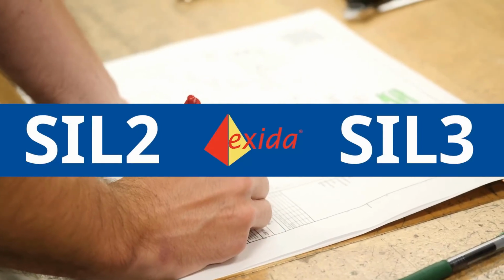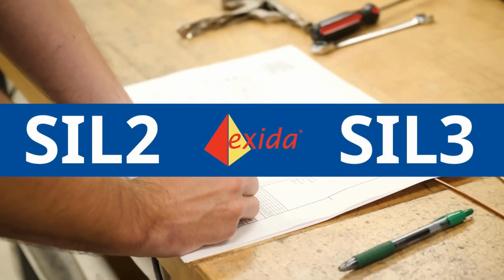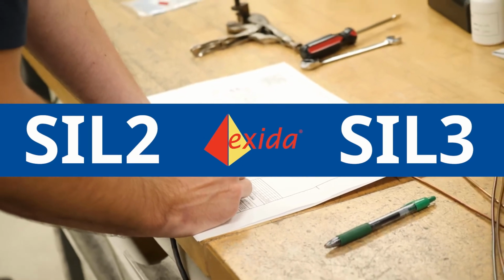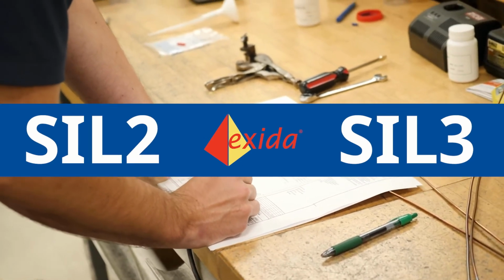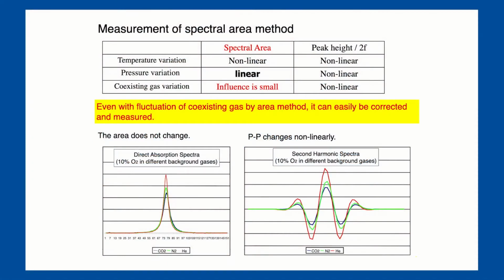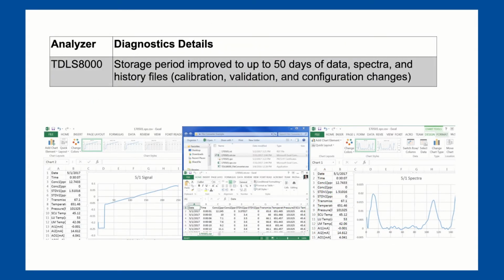The analyzer, just like our TDLS8000, is SIL 2 or SIL 3 with redundant or low demand mode applications, certified via hardware and software assessment for process safety applications. Our platform operates on the principle of direct absorption. The advantage of this over traditional 2F wavelength modulation is that we're much less susceptible to error due to changing background gases and pressures, unlike most other platforms. Another benefit of direct absorption is that we almost never require calibration for all applications. The TDLS8100 stores 50 days of data in spectral storage, meaning an upset during the weekend can easily be examined to determine the source of a problematic reading and validate analyzer functionality.